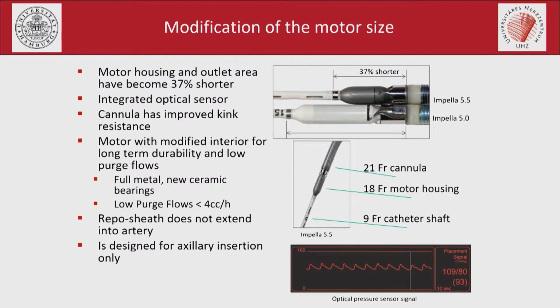Here you see a comparison between the 5.5 and the 5.0. The motor housing of the 5.5 is shorter. As I mentioned, it has this optical sensor. You see it on the picture below. The pump itself is stiffer, which made it even easier to implant. The 5.0 is also easy to implant. It has a newly designed motor, and it has a low purge flow, which allows longer support durations. And the repo sheath does not exist anymore, which should also facilitate long-term support with the 5.5. And importantly, it's designed for axillary insertion only, as I told you.